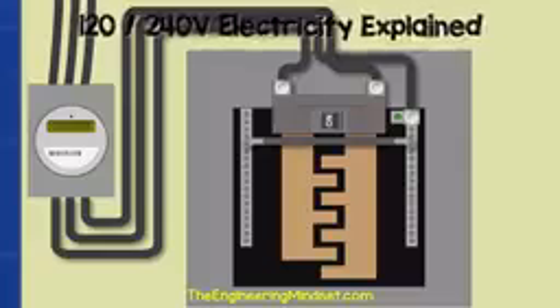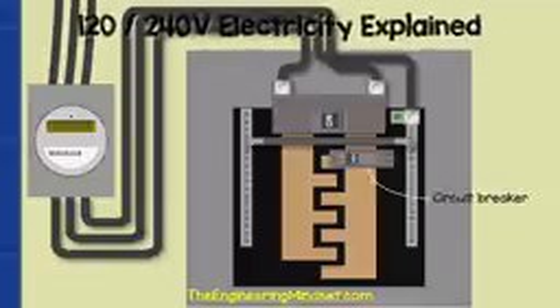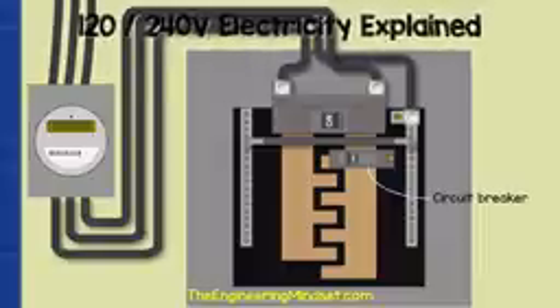Now coming back to the panel, connected to the bus bar, we'll have our circuit breakers. These will look something like this with this black plastic casing and a toggle switch on top. The circuit breaker controls the flow of electricity into individual circuits in the property. It can be manually tripped to cut the power, but it also has two important features.